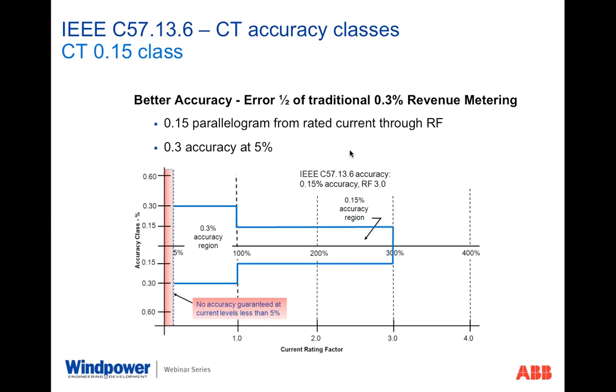Now going forward, when you look at the industry 12 years ago, we did not have a better class than 0.3. And then all of a sudden, in 2005, along came the IEEE C57.13.6 standard. And it says, okay, we're going to define a 0.15 class. Now, I have to tell you, manufacturers were already producing 0.15 classes well before that time. It just wasn't covered under the standard. We were meeting the functional needs of the users out in the industry.